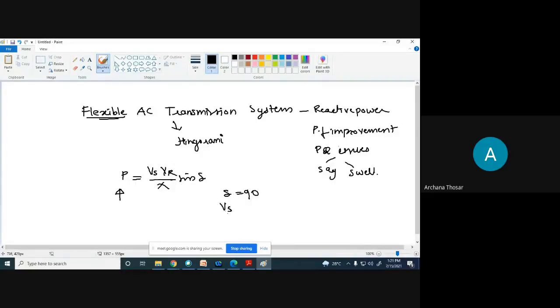You can increase the sending end voltage. You cannot increase the receiving end voltage, but you can decrease X, that is the reactance of the transmission line. So these are the three parameters which you can basically modulate or change so that the power transmitted over the transmission line will be maximized.